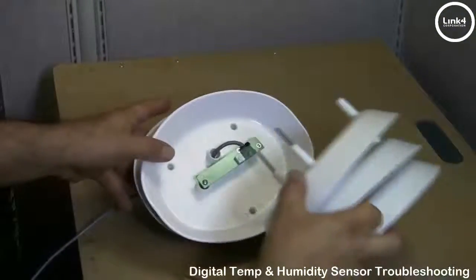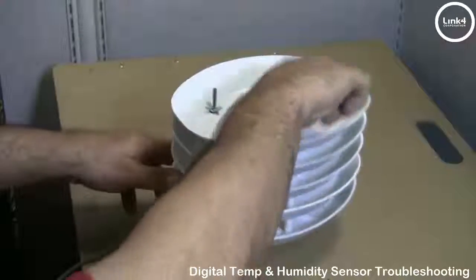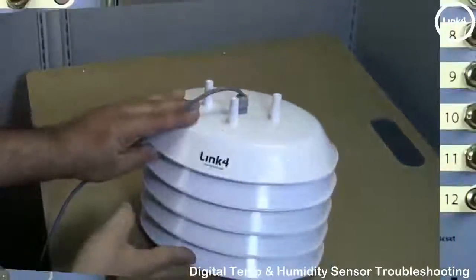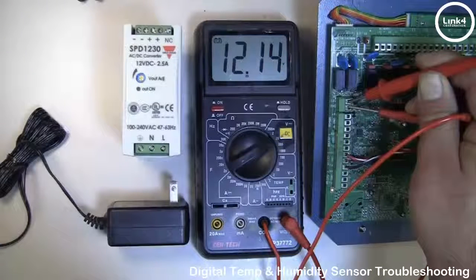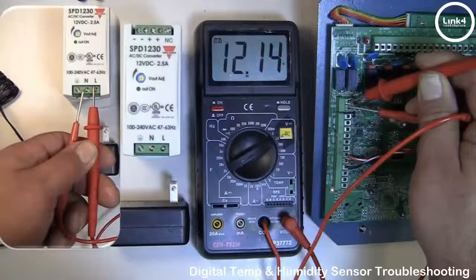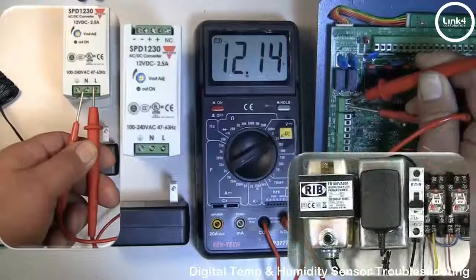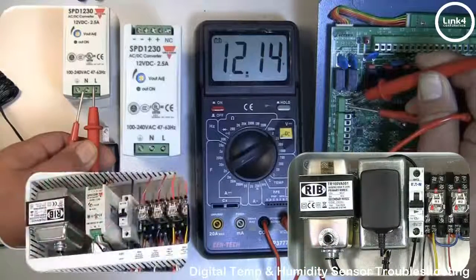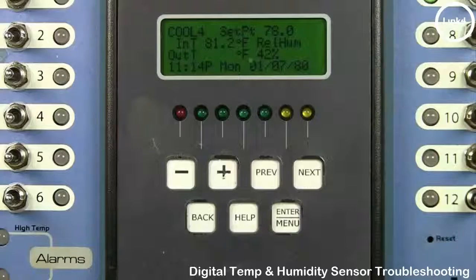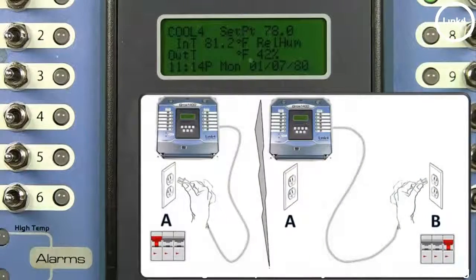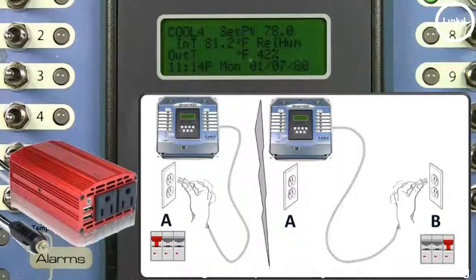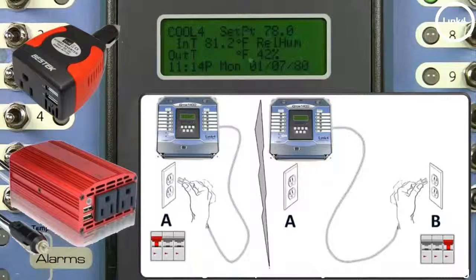You can also detach the sensor from its current location and put it right next to the controller itself to see if the readings recover. Next, if you're still experiencing sensor issues, you may want to measure the step-down voltage from the 12-volt DC power supply. Marginal voltage can also be a factor on the sensor's functionality as well. If you have a 12-volt power cube and it's marginal, you want to replace it. If you have a 12-volt DIN rail power supply and it's marginal, you can dial up the voltage to the correct value. And finally, you can try powering the iGrow itself from a different circuit entirely, using an extension cord across the way or even an inverter plugged into a car on site to see if the sensor stabilizes.